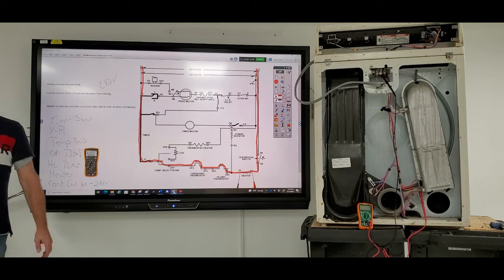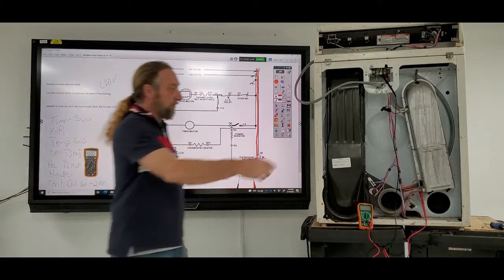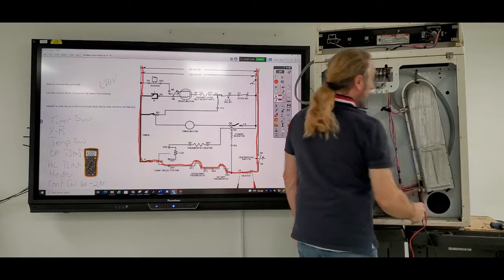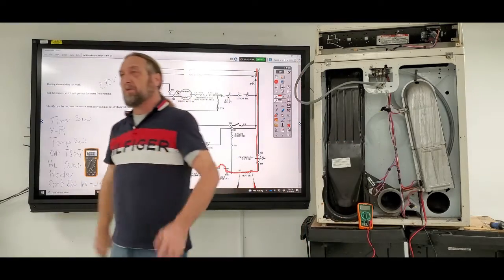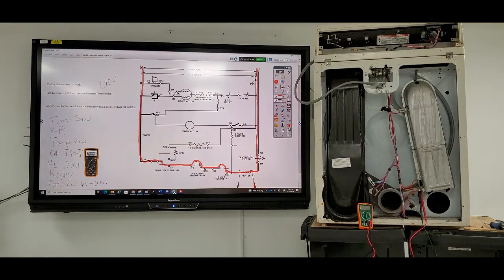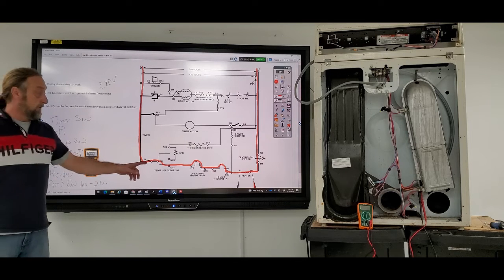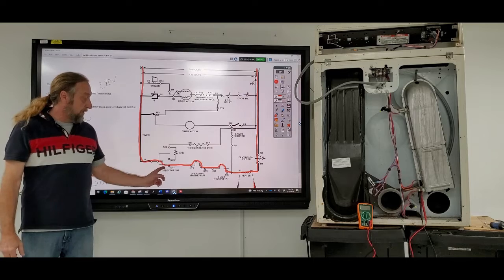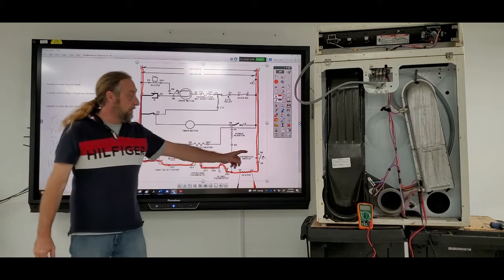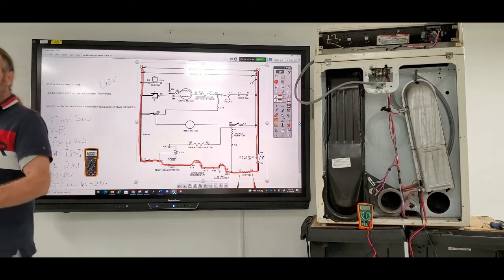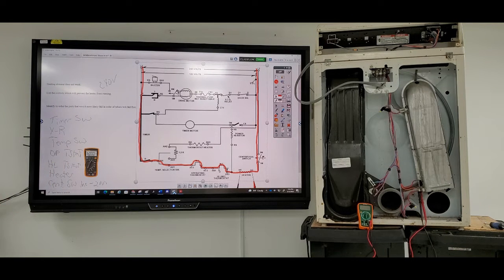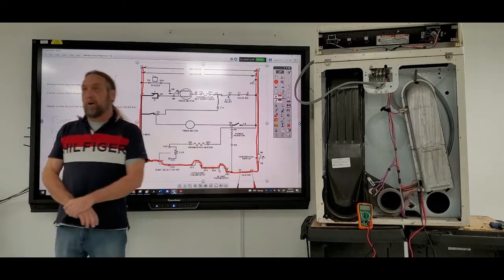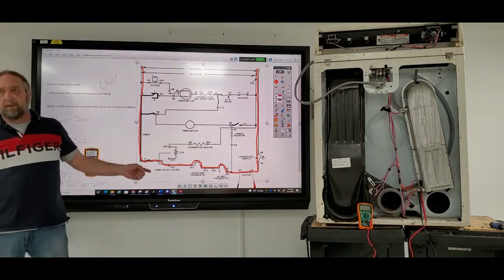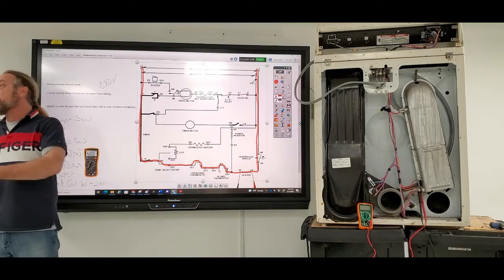I don't have 240. Now I got my meter leads both on the heater. I turn the dryer on, my meter says 0 volts, so that means I'm not getting power. It could be the timer switch, selector switch, operating or high limit thermostat, or centrifugal switch. They're all back there, I can ohm them all out, sure. But what if I told you with one test you'd know which way to go, whether it's one of these or a motor problem? Could you imagine testing all these for ohms, and then finding out you need to go to the motor? You took all this time testing these.